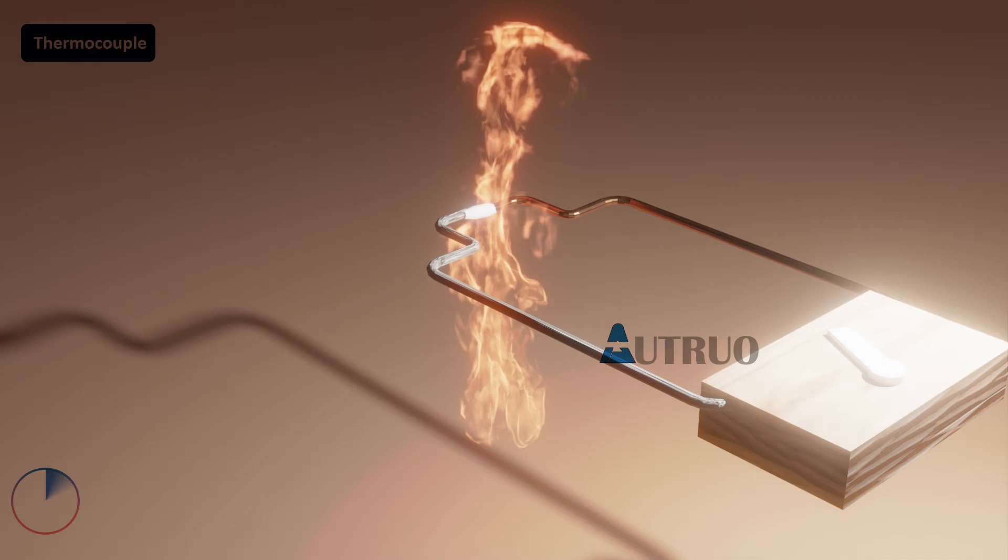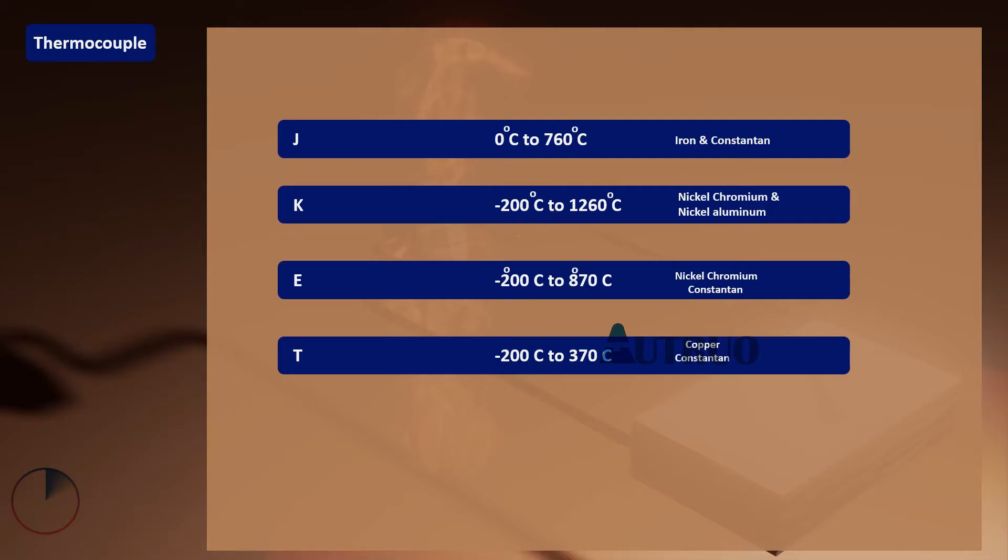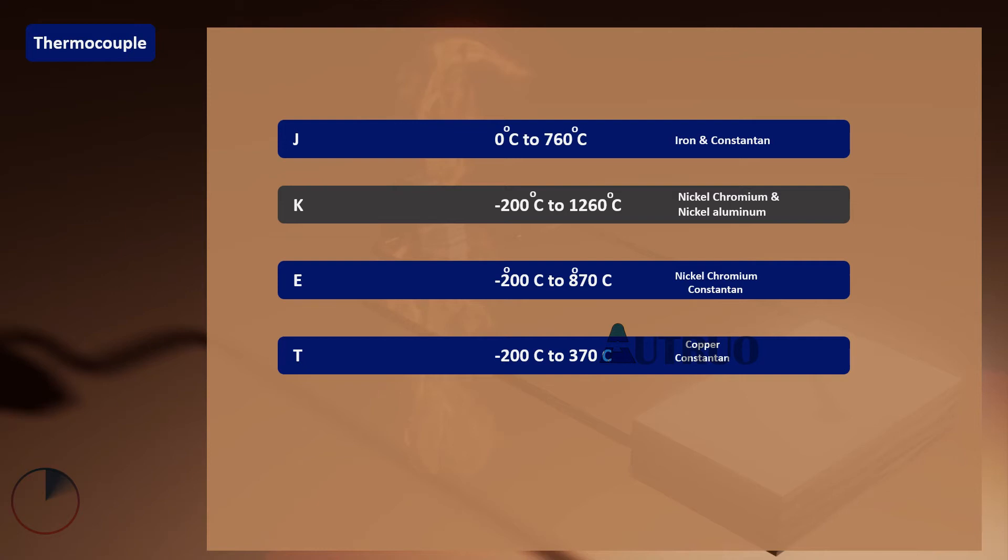Thermocouples come in different temperature ranges. These ranges are tagged by letters indicating their ranges. The most common type is Type K, which is nickel-chromium or nickel-aluminum. This type can measure as low as minus 200 degrees and as high as 1260 degrees.